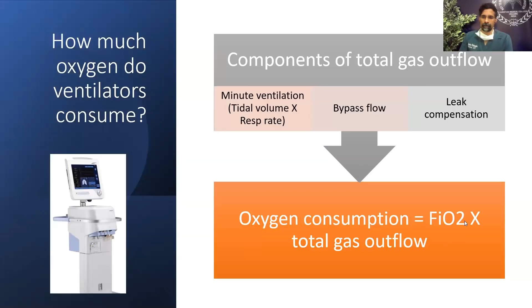And the third is leak compensation, in the sense that all systems have some small amount of leak, and most modern ventilators will increase the flow to compensate for this leak. So if we know these three components, it is very easy to calculate the total gas outflow. And of course, the fraction of oxygen in this total gas outflow is the amount of oxygen consumed.